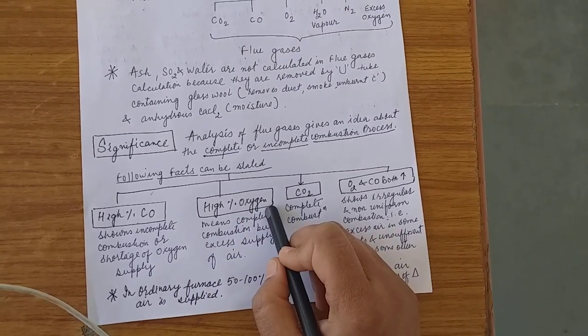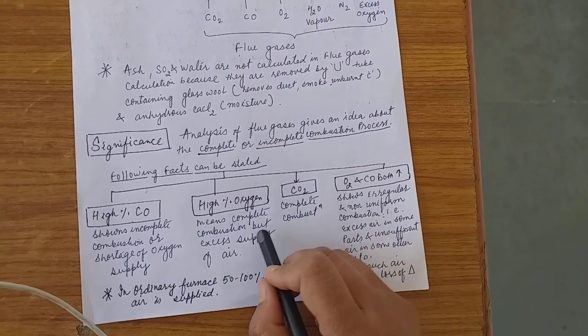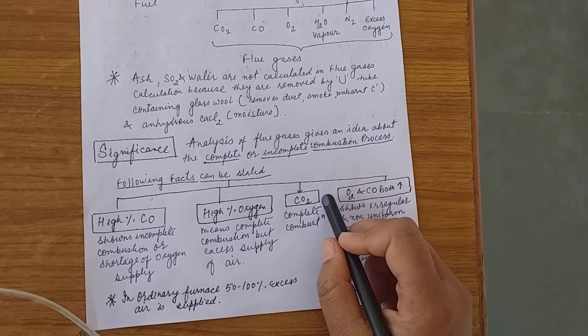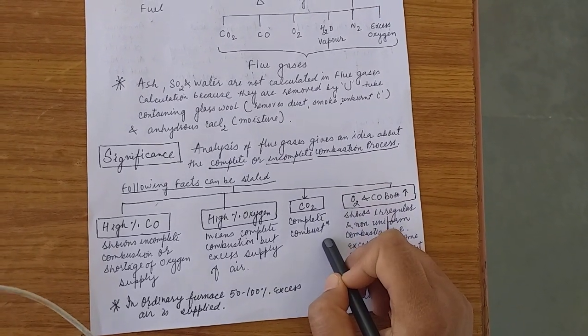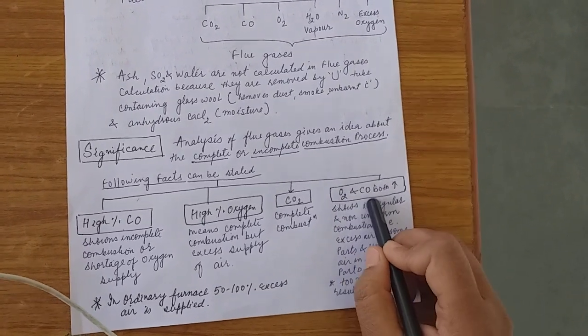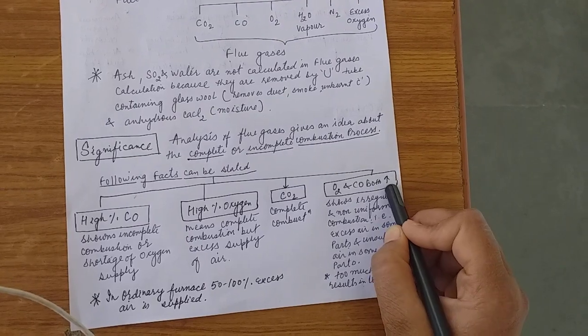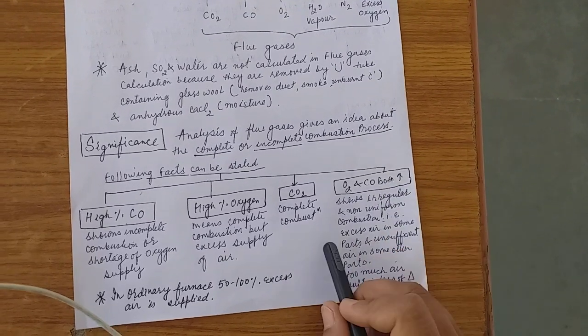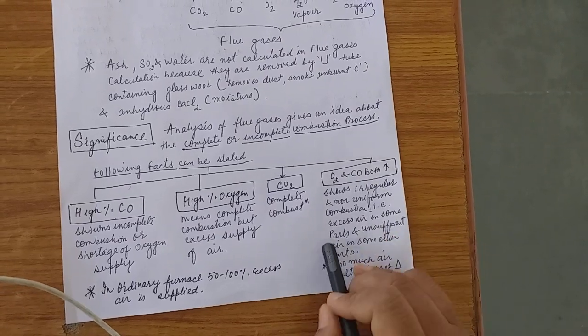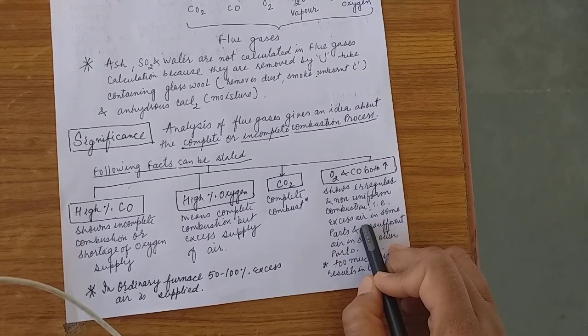If there is a high percentage of oxygen, it means complete combustion but excess supply of air. If there is CO2, it shows complete combustion of the fuel. If there is O2 and CO both in high percentage, it shows irregular or non-uniform combustion.